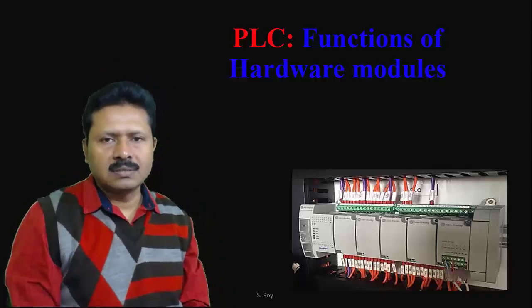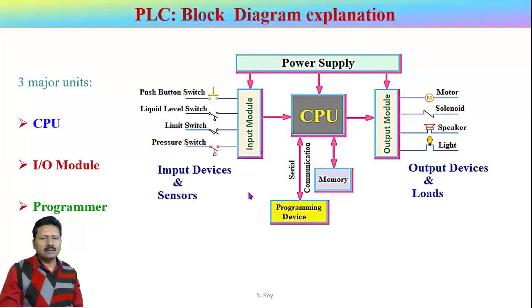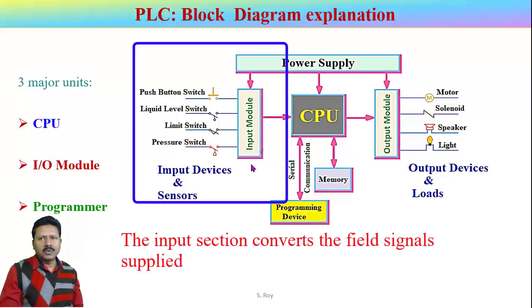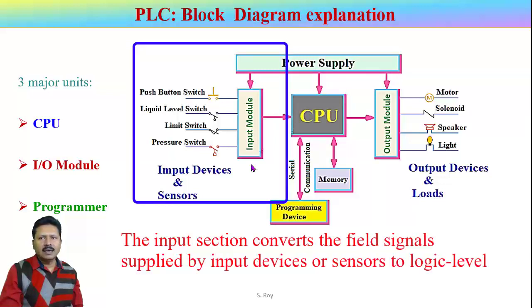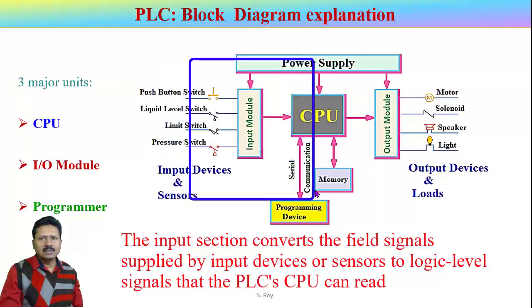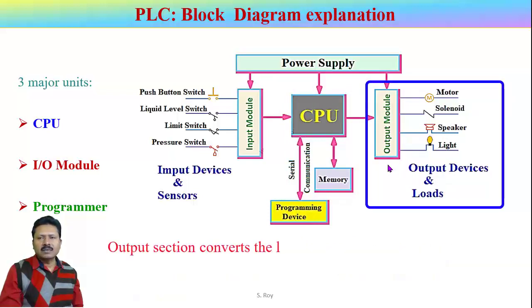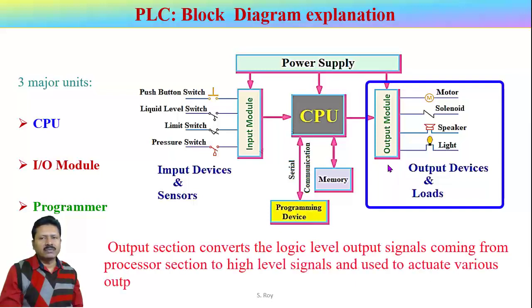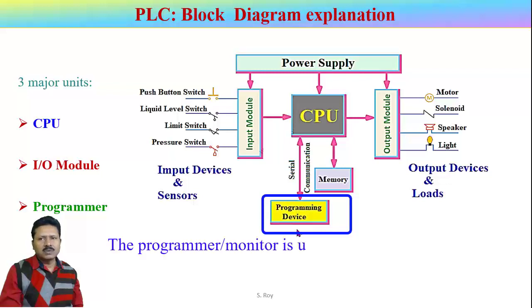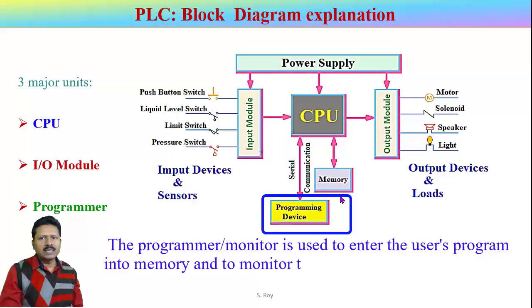This is the block diagram representation of PLC. The main sections of a PLC are CPU, input module, output module, and programmer. The input section converts field signals from input devices and sensors to logic level signals that the PLC CPU can read. The processor reads these inputs, processes the signals, and prepares the output signal as per the program. The output section converts logic level output signals from the processor to high level signals to actuate output field devices. The programmer or monitor is used to enter the user program into memory and to monitor execution of the program.